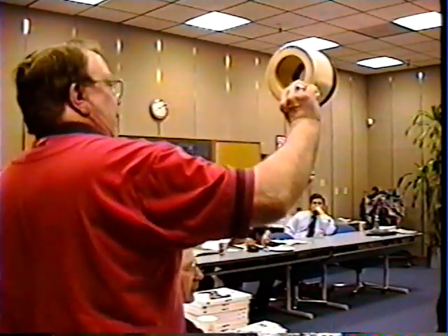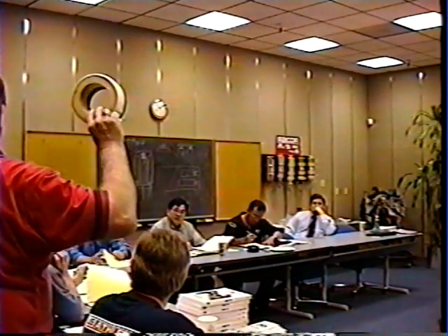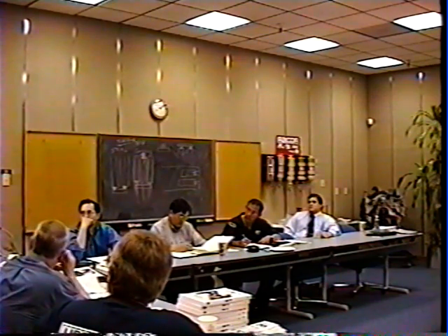When we did our API test, because our elements were so well constructed, we passed the 75 PSID destruction test, and we did that without a center tube. You'll notice our API elements have no center tube. We're the only folks in the industry who don't have a center tube or some type of material inside of the media to give it strength. And what we found here is we did this with a 44-inch long element, that it flexed, it moved around, and we torqued 3 times till we finally got our torque values to stay. So torquing is very important.